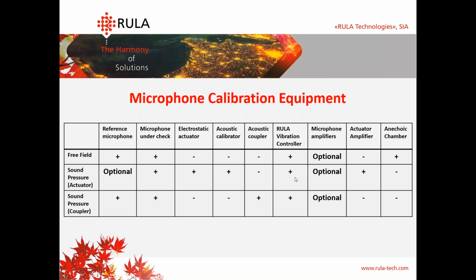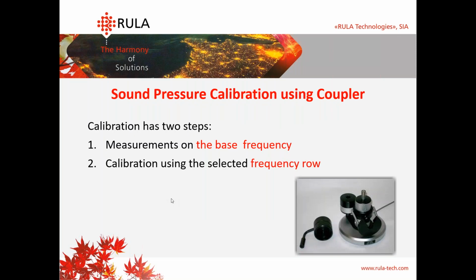As always, you need our controller, and amplifiers for microphones are optional, and you need an actuator amplifier. But we can also use a coupler. In that case, we don't need an actuator or calibrator. I will show you on the screen how the coupler looks. And this is the main table for equipment. So the main way, the fastest and the easiest way, is to use the sound pressure method with an actuator.